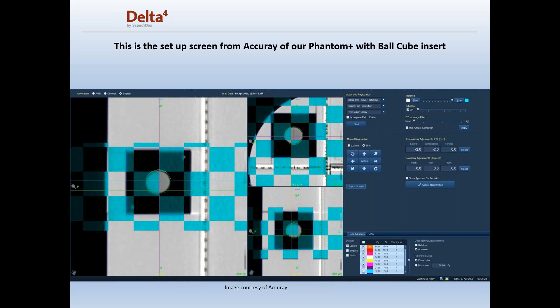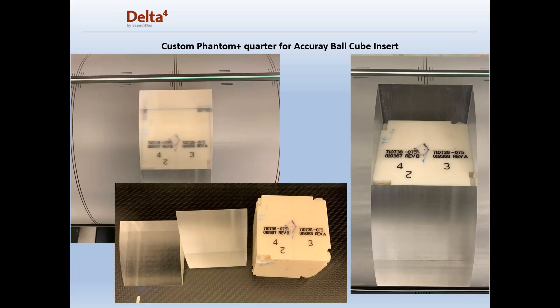With our system, the diodes are positioned at the coronal and sagittal planes internal and at isocenter of the phantom, which allows for inserts like the ball cube to be inserted into the upper left-hand quadrant of the phantom. This shows where they're going to start a patient QA, using KV imaging to position the phantom on the couch. When the ball cube is not being used, there's an acrylic replacement so it stays solid PMMA material.